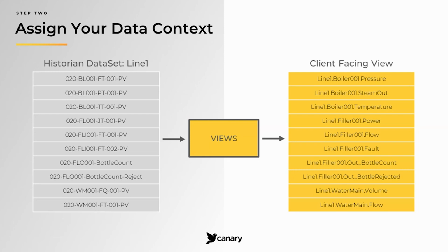And to create rules within the virtual views, we use regular expressions, or as we say in the industry, regex. It's a sequence of special characters that define a search pattern. And this powerful tool allows you to use existing logic in your tag naming or metadata to make changes in mass. It's similar to a find and replace in a word processing document. You use regex to identify groups of tag names and apply universal changes.